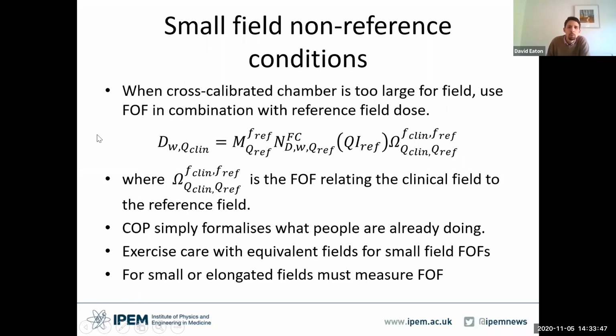When our cross-calibrated chamber is too large for the field, then we may need to use our field output factor in combination with a reference field dose, because we can't be sure that there's charged particle equilibrium if our field is smaller than the lateral charged particle equilibrium radius. So essentially the code formalizes what you've already been doing. You measure an output factor. And if you have tables of output factors, if you know the equivalent field size, you can use that, but this approach is limited because the chamber response might be different between a long thin field with the same area and a small square field with different perturbations. So measurement is recommended.